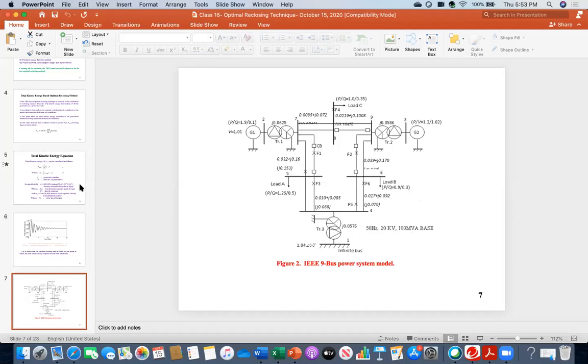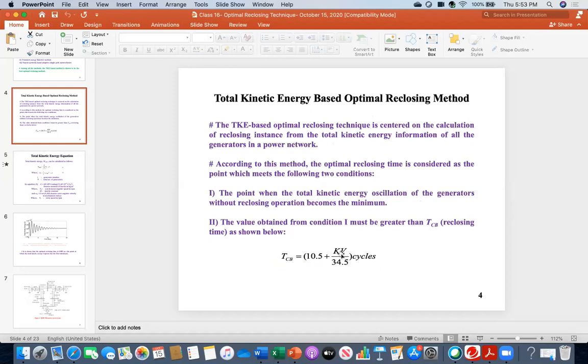For the system you are calculating, of course, that information will be given to you. So for example, it is 20 kV, and that number is directly expressed in kV. Therefore, here you have to put 20. Everybody calculate on your calculator. If you put 20 there, what will happen? I am doing 20 over 34.5 and then plus 10.5. So you get 11.079, and this is in cycles.